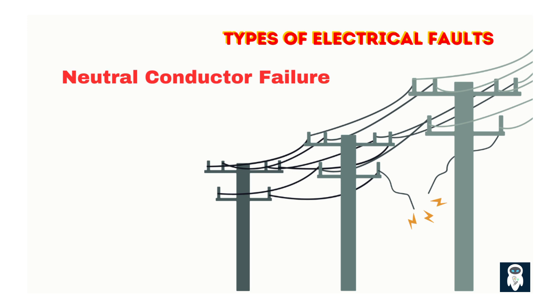The last fault type is neutral conductor failure. In low-voltage networks, a broken neutral conductor can unbalance the system — some phases may experience higher voltages while others drop. This imbalance can disrupt power distribution and create safety hazards. This type of fault can significantly impact the reliability of the electrical system and needs to be identified and addressed promptly to prevent further issues.